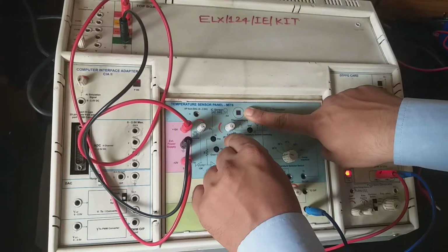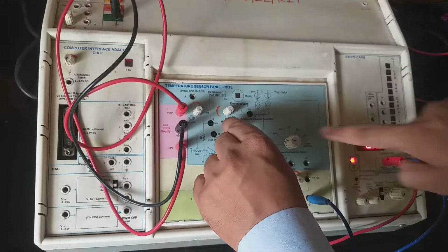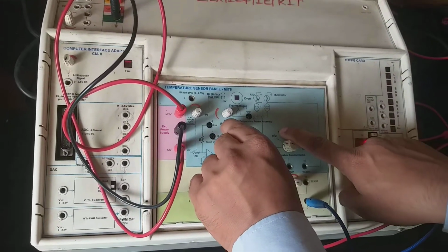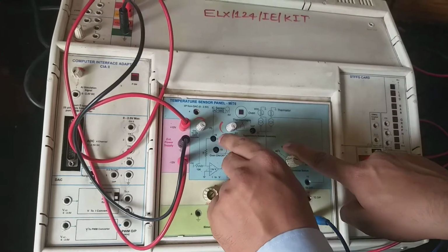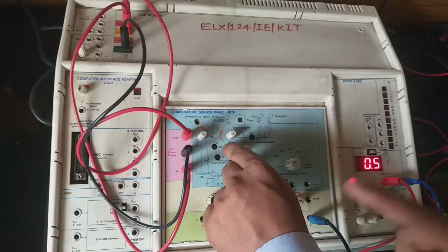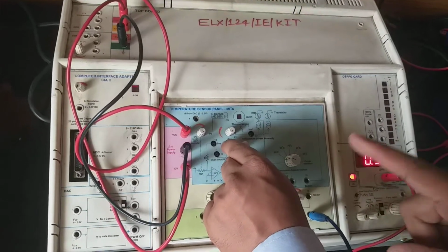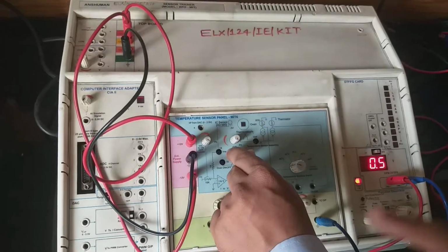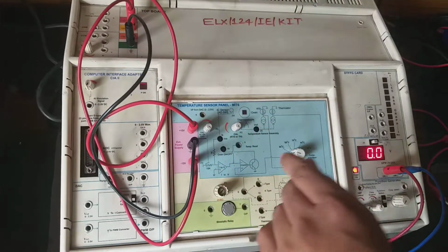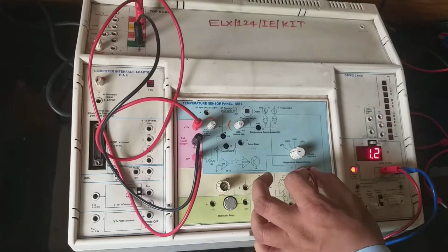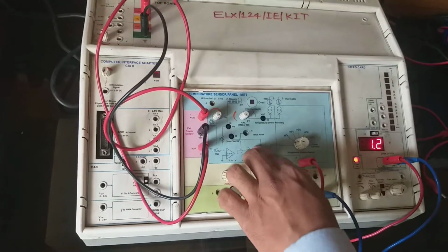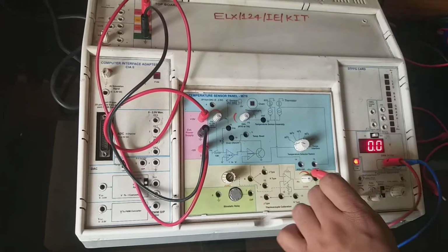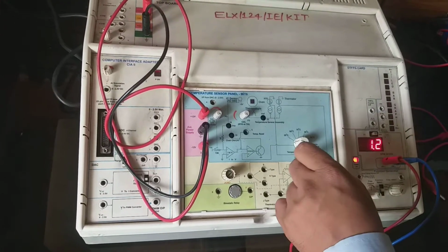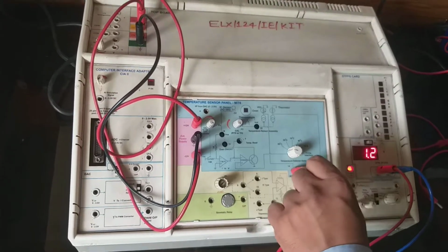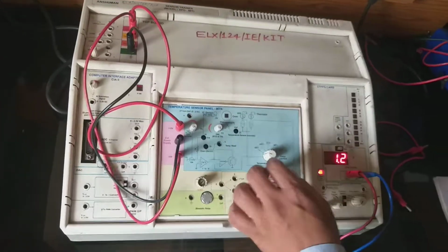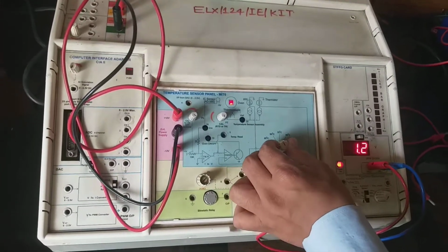Here the temperature readout can be measured using this, that is 0.55 for 55 degrees Celsius. Within this range the oven will turn off, indicating that the set point temperature and actual oven temperature are nearly equal. At this point measure the voltage at the output of the RTD. Once both the voltages at the comparator become equal and the oven turns off, immediately measure the voltage at the RTD output. Measure the RTD output voltages for different temperature set points, that is for 55.